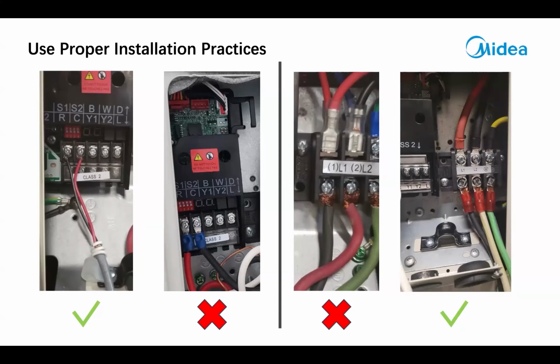Since we are running communication wiring, and in most cases in a retrofit application we'll have existing 18 gauge wire from indoor to outdoor, and we show 18 gauge stranded shielded wiring, are we okay with running standard 16 gauge? Yes, you are okay. That's what we recommend, 18 gauge stranded shielded cable for our communication cable. However, if you're on a retrofit where you cannot run a new shielded cable, you can use the existing thermostat wire. Just be aware that you could experience some interference issues.